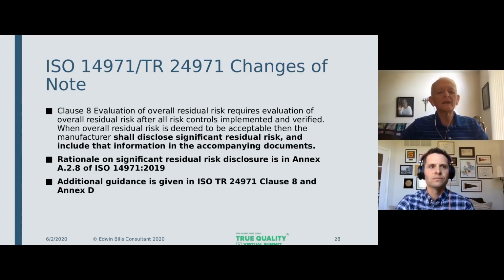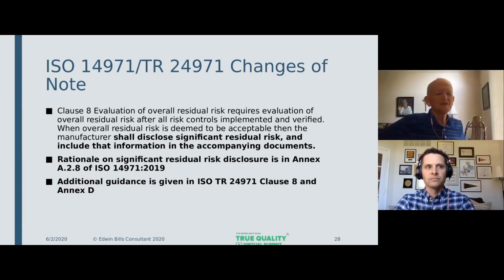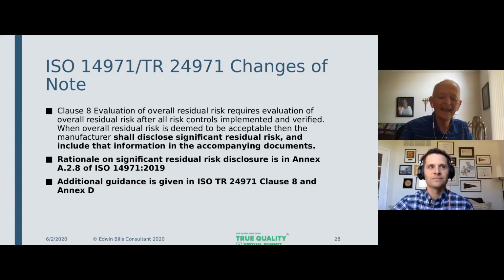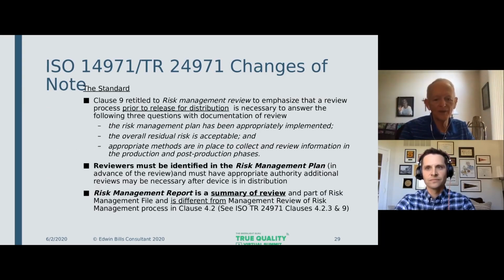Then clause 8 is evaluation of overall residual risk, and it requires the evaluation of overall residual risk after all risk controls are implemented and verified. And it requires the manufacturer to disclose, notice this word, significant residual risk. That's what you have to decide as a manufacturer, what's significant. You have to disclose that significant residual risk in the information in the accompanying documents that go along with your product. And then there's rationale in Annex A.2.8 of 14971 and guidance in 24971, Clause 8 and Annex D. So there's a whole lot of information to help you on this.